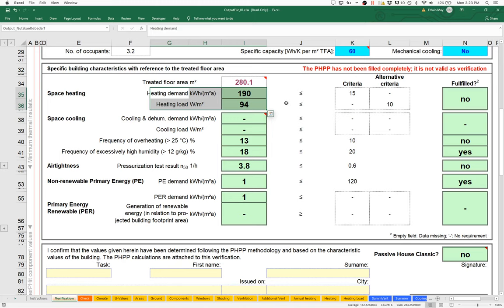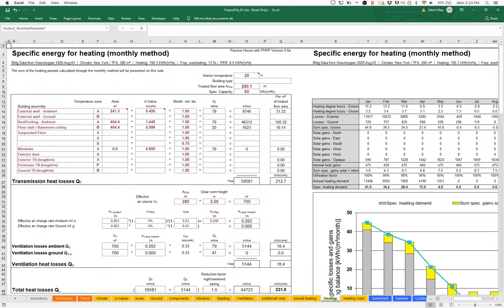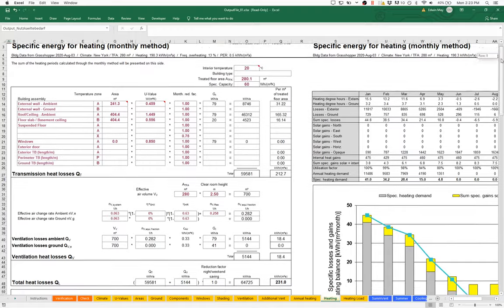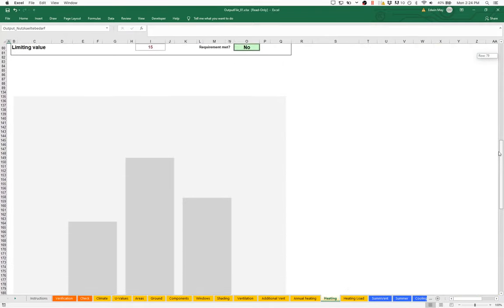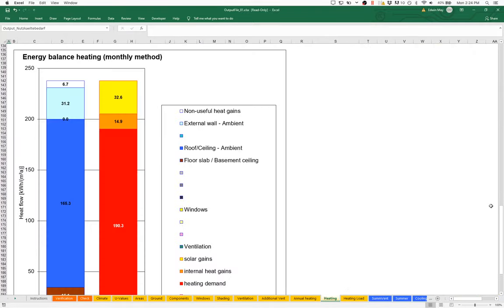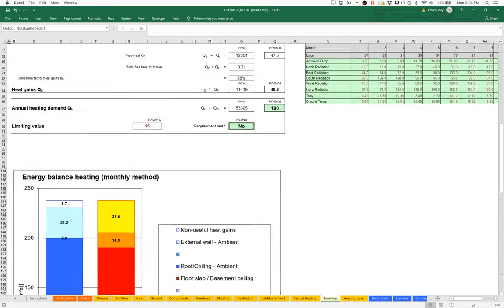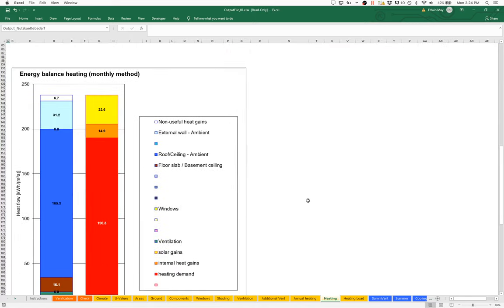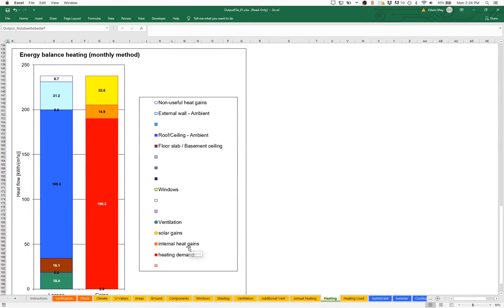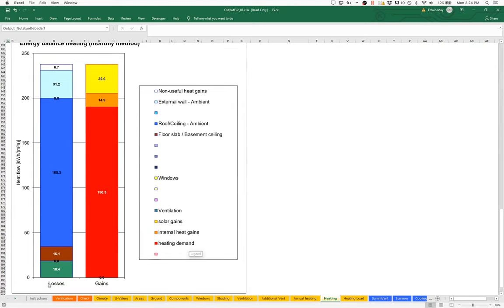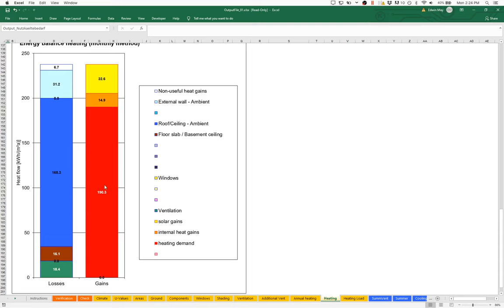Why do we have such a high heating energy demand on this project? The way we can determine that is by going into the heating worksheet. There's some good breakdown information here. This is all summary data, none of this is input. It's going to tell us a little bit about how our building is performing. The place we would usually start is down here at the bottom with this summary graph. Let me zoom out so we can see that more easily. Here's our energy balance graph: losses on the left, gains on the right. We have a lot of losses and not very many gains, which means we have a resultant heat demand of 190 kilowatt hours per square meter.